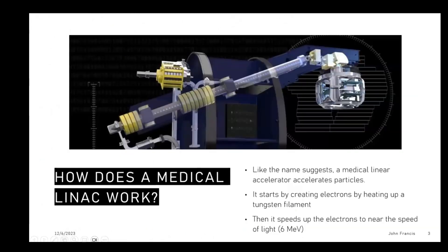So how does a medical LINAC work? This is kind of an internal view of a medical LINAC. On the left side is where they generate electrons — they heat up a tungsten filament and it starts emitting electrons. This big tube is what accelerates the electrons. They send in radio waves and the electrons accelerate to close to the speed of light, or around 6 MeV. Then they go over to the LINAC head on the right.